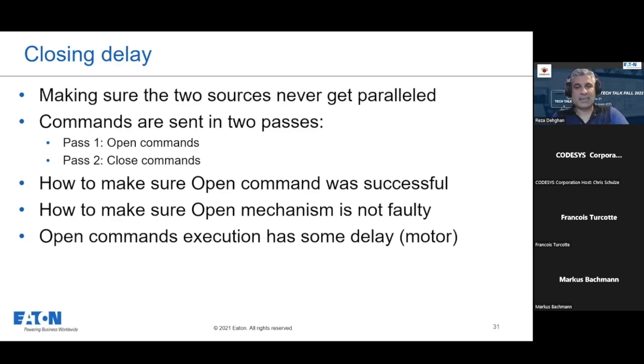Open commands execution has some delays. That was the source of the problem, because waiting for confirmation, as in many languages, like C++ for example, you can do something and then wait for a specific time, 1 second, 2 seconds, 3 seconds. This is not possible in CODESYS. CODESYS doesn't support, at least natively, waiting per se. So, next slide.